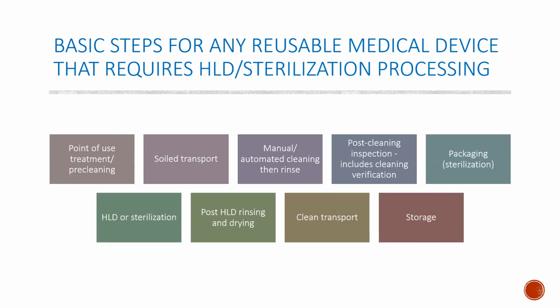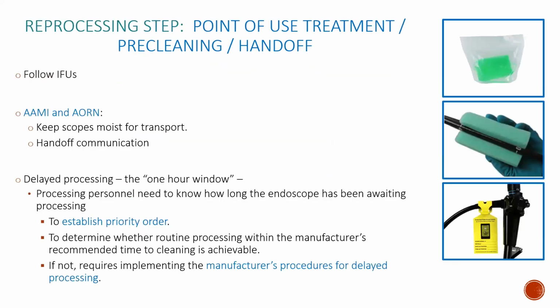To further help address the objective, let's reference the steps of processing. What you see here is very much an oversimplified list to represent the basic steps common to both HLD and sterilization, from clinical use through processing to storage. What's done at the bedside was historically called pre-cleaning. It's now referenced as point of use treatment. Important points at this stage. This is the initial removal of organic material, and it's critical to decrease the bioburden load for any subsequent steps, be it high-level disinfection or sterilization.